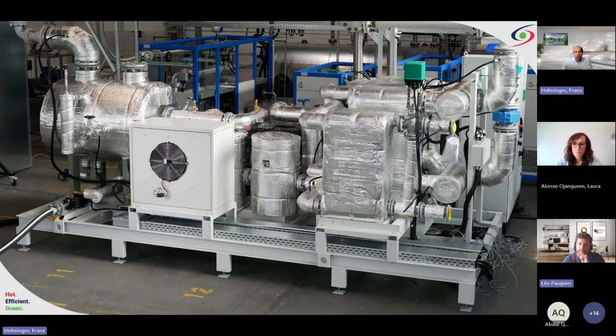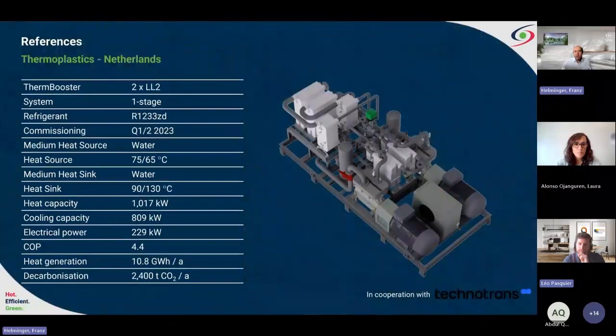The next reference is an LL2 we placed in 2023. 2 of them, it's also a 1-stage system with the R1233zd refrigerant, and with the operating conditions at the heat source of around 75 to 65, so inlet to outlet, generating heat up to 130 degrees C. On the right-hand side, you can see the design of the heat pump with 2 compressors on the frame. With these 2 compressors, you get up to around 1 megawatt and a COP of 4.4.